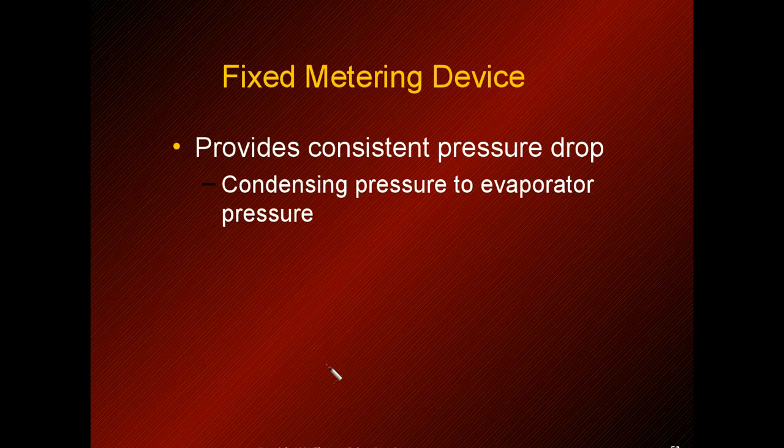The cap tube provides a consistent pressure drop. As the condensing pressure goes up, the evaporator pressure will go up, and vice versa — when the condensing pressure goes down, so will the evaporator pressure.